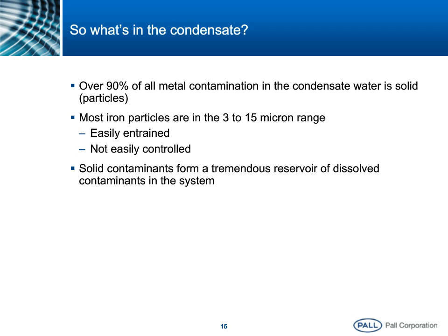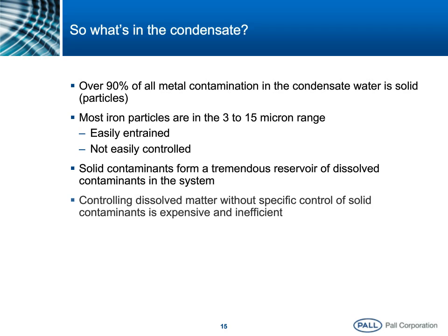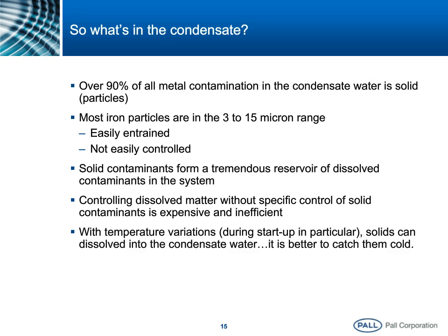So controlling dissolved matter without a specific solution to address this huge amount of solid contaminants is usually very expensive and quite inefficient. And when temperature plays a part in either the outages or during startup, these solids can tend to redissolve in the condensate water, and it's better to catch them cold.